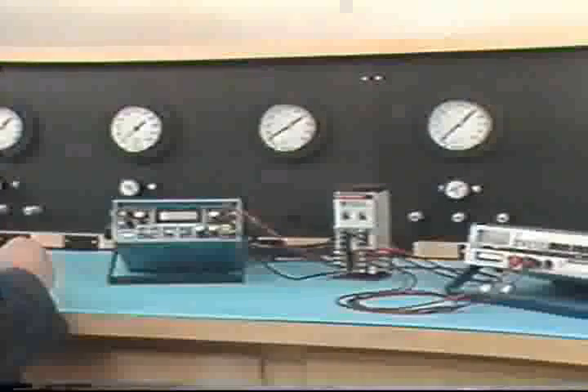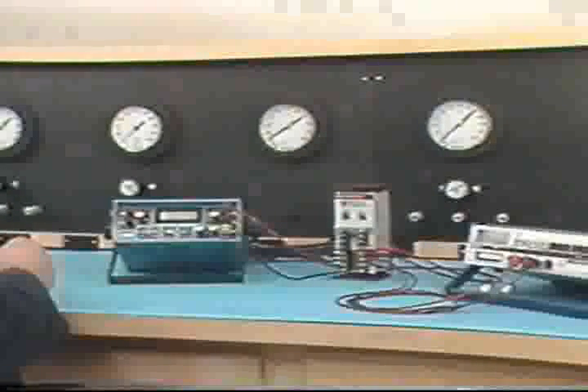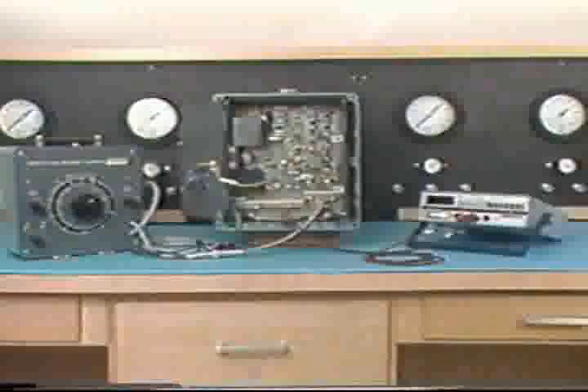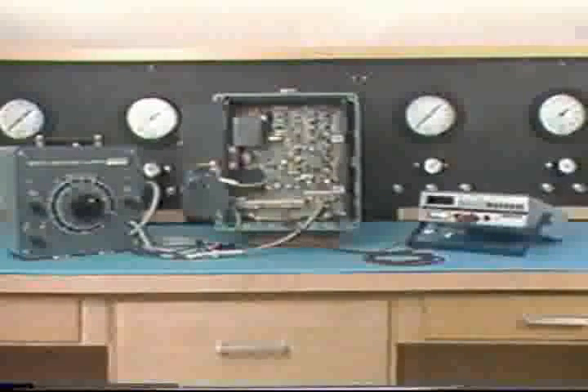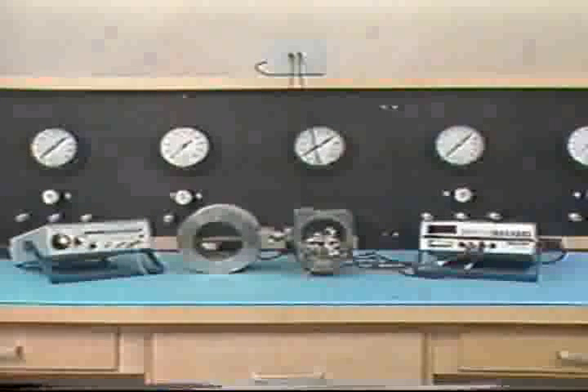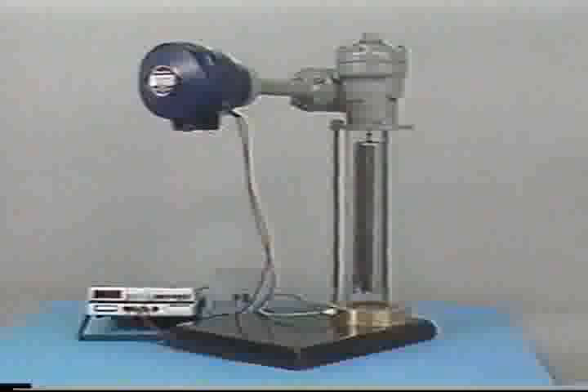In this program, we've seen that flow can be measured using differential pressure. Sometimes a pressure transmitter uses a square root extractor that's located in a separate location in the loop. In this situation, the square root extractor must also be calibrated. When calibrating a flow meter, once the test equipment has been set up properly, a 5-point check is made to determine the instrument's accuracy. Often, special calibrators are used as input standards.